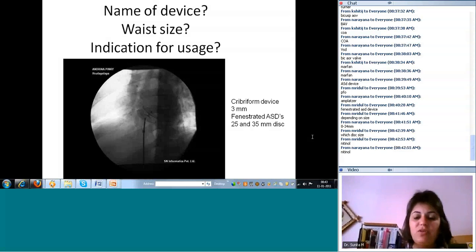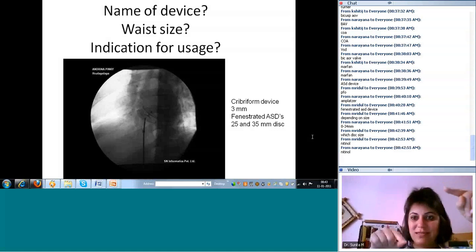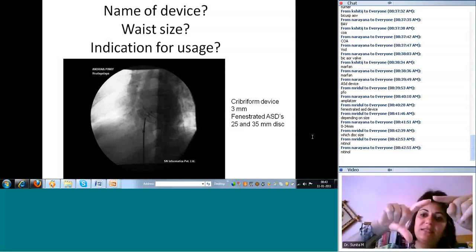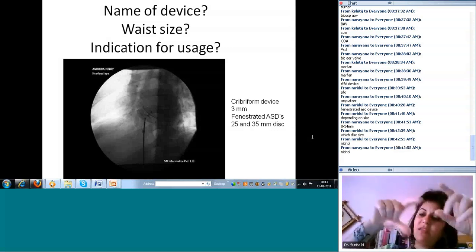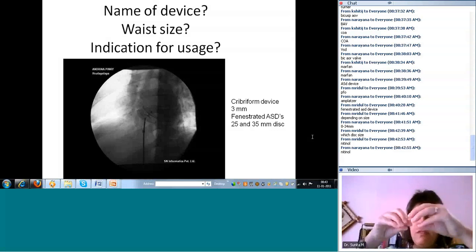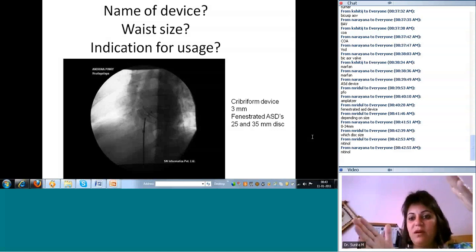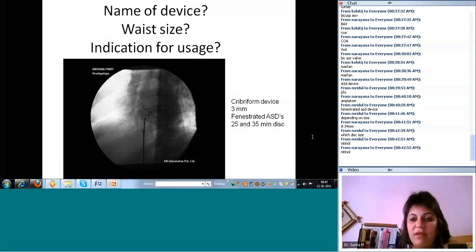Then it depends on the fenestration. So you take the most distant fenestration on this side to the most distant fenestration on that side. You measure that distance. If that distance is say less than 25, then you can use a 25 device. If they are separated by 30 millimeters between the two here, then you need a 35 device. So that's how you will decide on the device size, the same way you do with your ASD device.